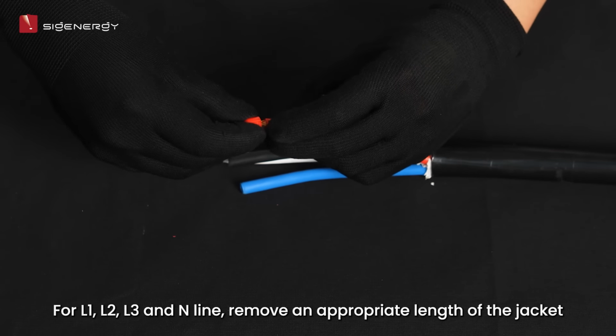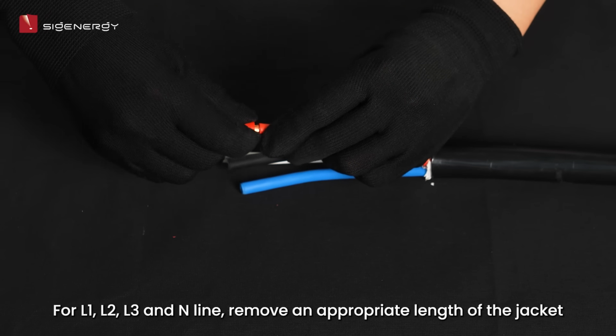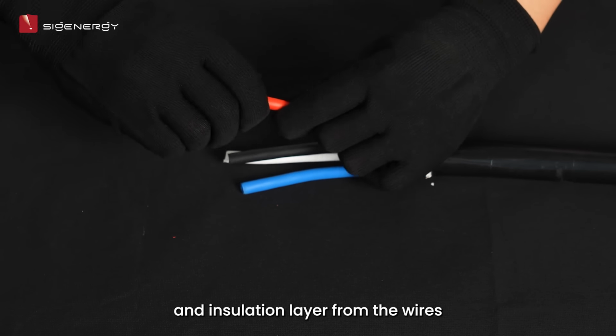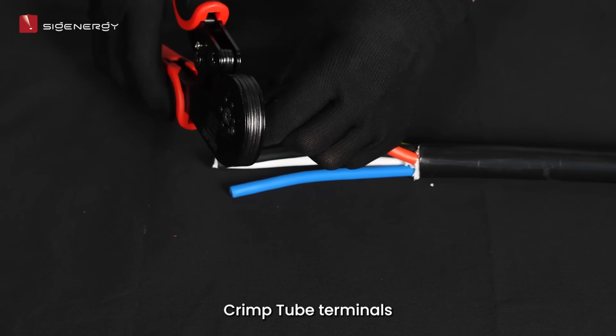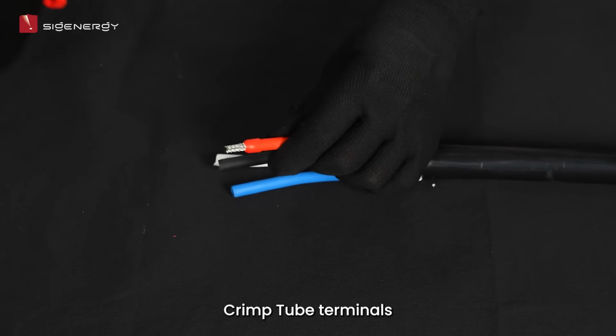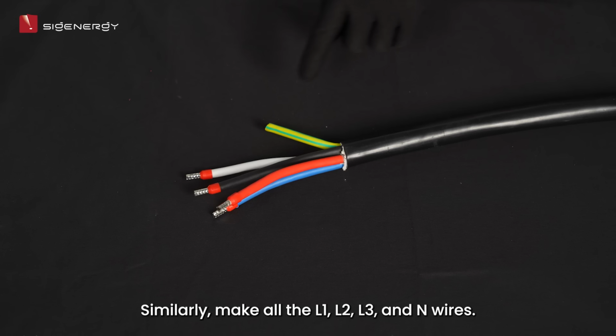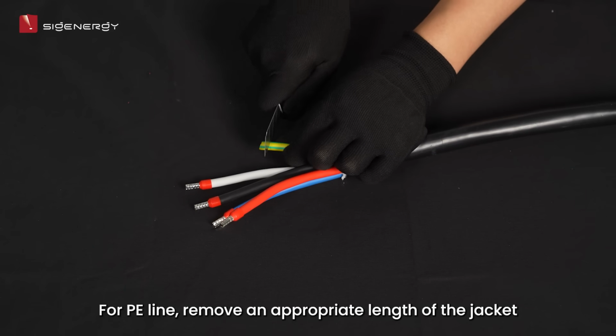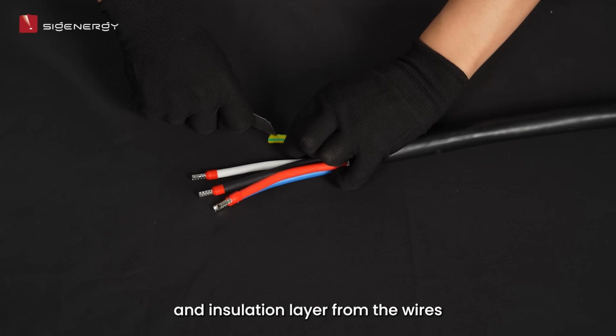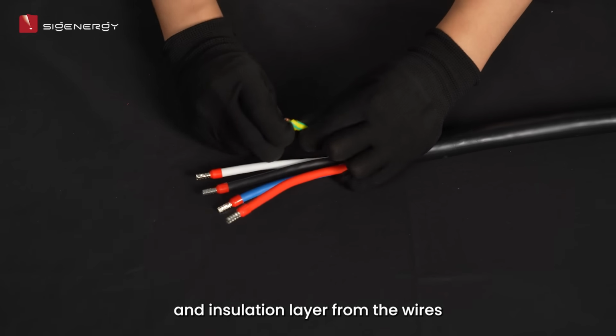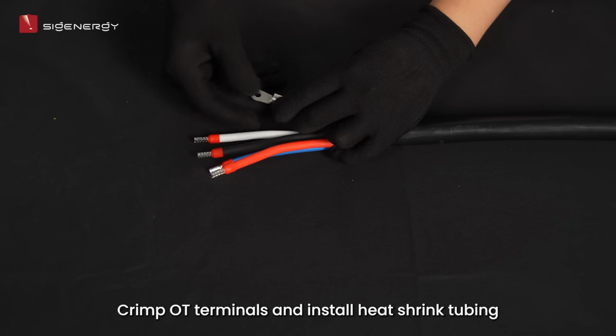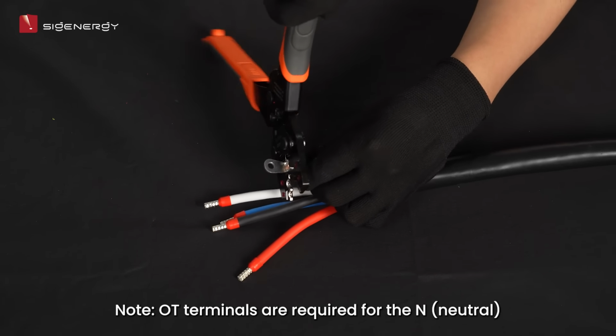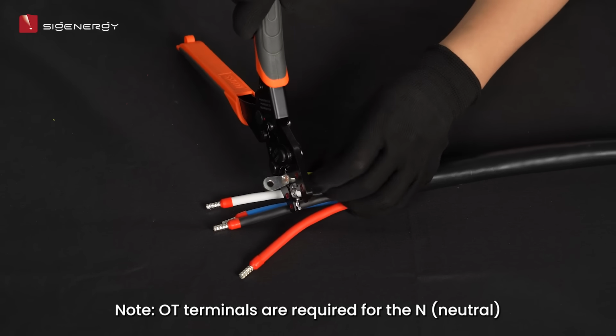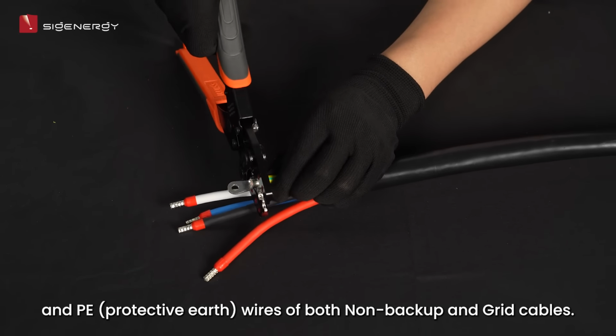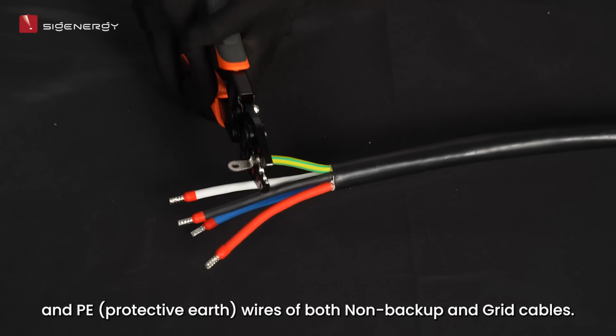For L1, L2, L3, and N-line, remove an appropriate length of the jacket and insulation layer from the wires. Crimp tube terminals. Similarly, make all the L1, L2, L3, and N wires. For PE line, remove an appropriate length of the jacket and insulation layer from the wires. Crimp OT terminals and install heat shrink tubing. Note, OT terminals are required for the N, neutral, and PE protective earth wires of both non-backup and grid cables.